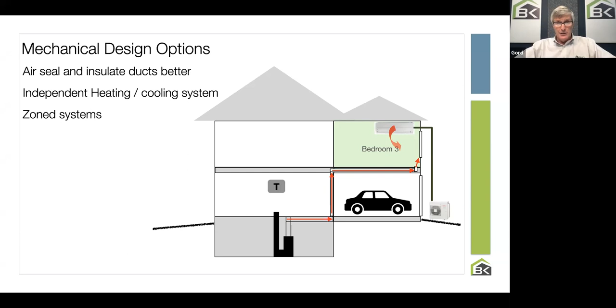Duct sealing - if I'm going to be really blunt, ducts leak. Every duct system I've ever measured, even now that we do duct sealing in houses, is 10 to 15% leaky. So 10% of the air you thought was coming out this duct isn't, and it's at 10% lower temperature, so we're already up against it in terms of managing comfort to those spaces.